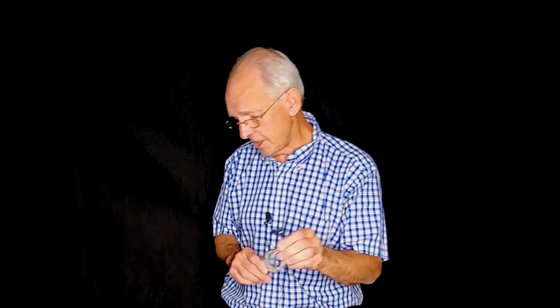stop. So this is a through beam sensor using light. One side shoots a beam of light and the other side receives it. And this is used with a blade or a disc that rotates through the sensor to tell you how fast something's turning or when it's reached the end of its travel. It's non-contact because of the beam, and they can operate very fast. The downside is they aren't very good in a dirty or dusty environment. That's when the inductive proxies really take over, because the inductive proxies are very, very dirt insensitive.